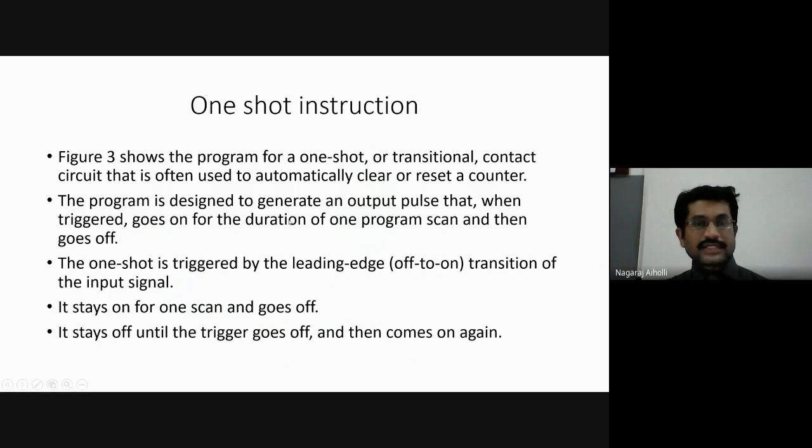The program is designed to generate an output pulse that, when triggered, goes on for the duration of only one program scan time, and then becomes off. When the instruction is activated, it will remain activated for only one program scan time duration, not after that. After the one program scan time, it will automatically become off.